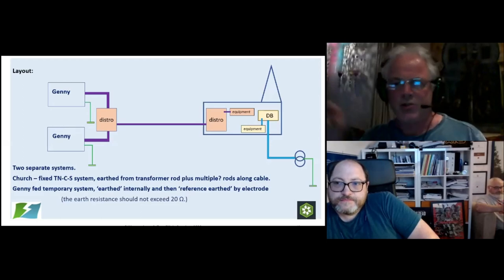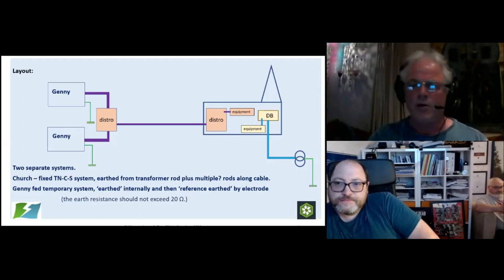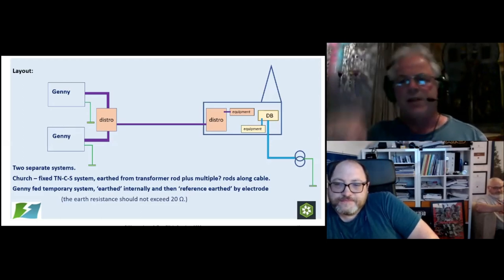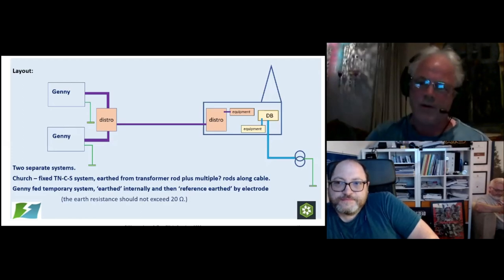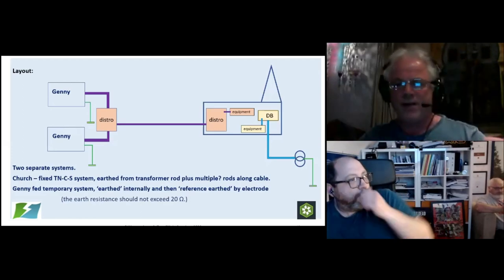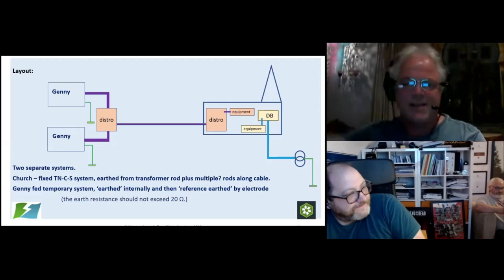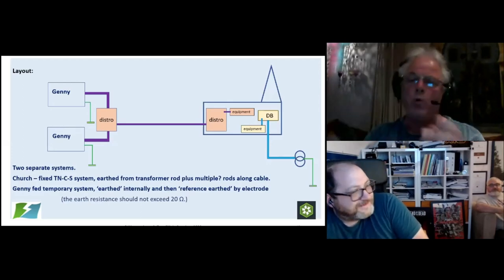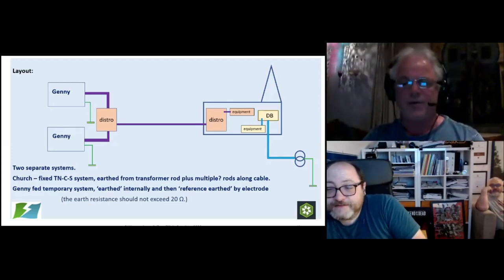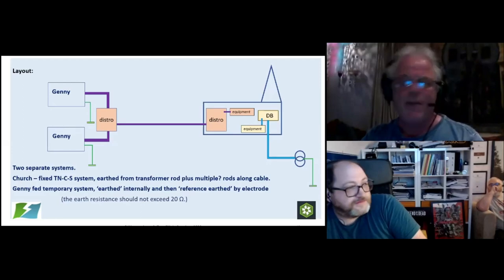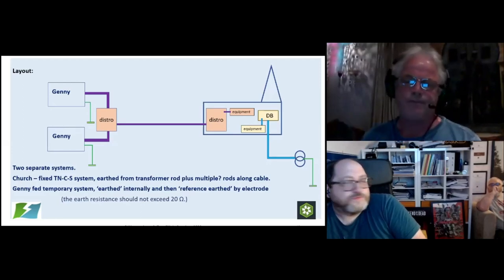However, that earth isn't true earth, and the reason we put an earth rod in is to reference the generator earth to true earth. So if we've got a number of generators on a site, or a generator at a fixed installation, all the earths will be referenced to true earth. They're all at the same starting point. That will minimize differentials in voltage.